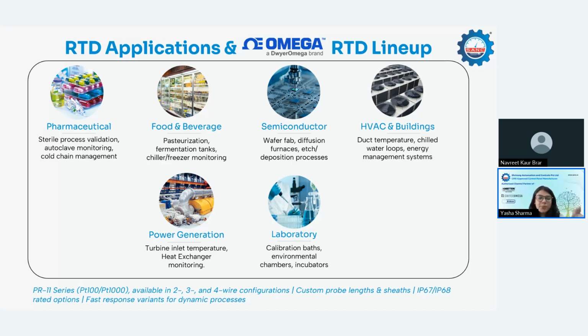Omega has the PR11 series, based on PT100 and PT1000 according to your requirement. These are available in 2, 3, and 4 wire configurations. If the probe length does not suit your need, customization is available. Sheath material can also be customized, and IP67 and IP68 rated options are available. There is also a fast response variant for dynamic processes.